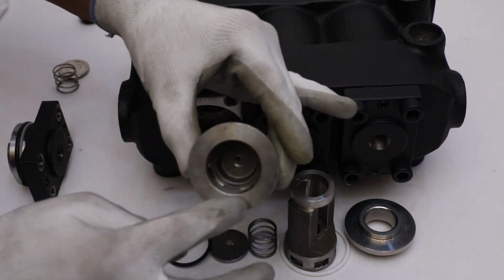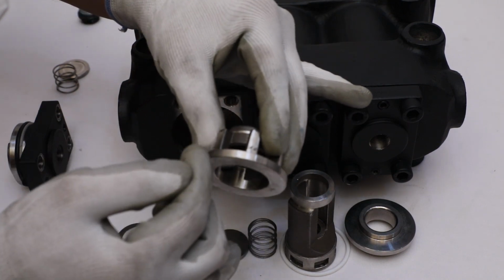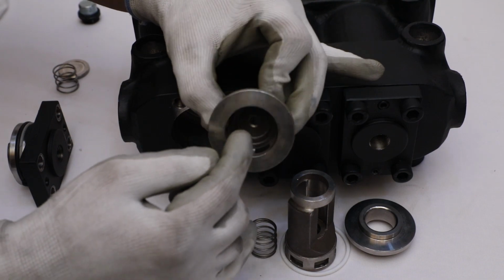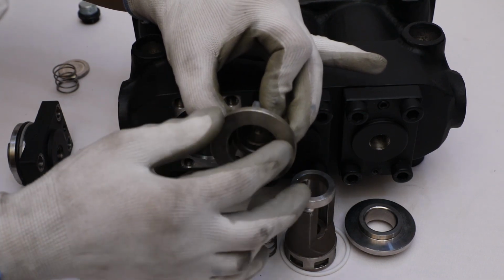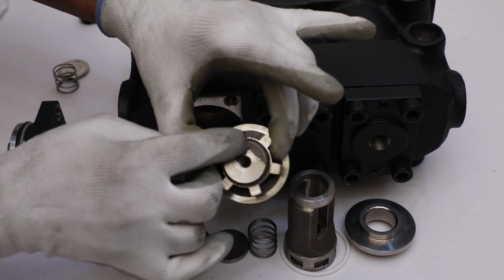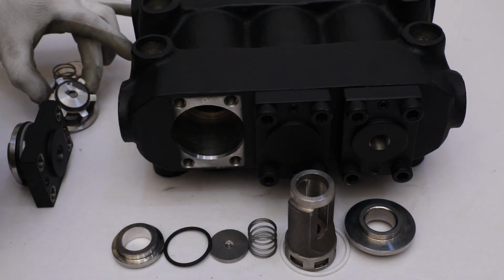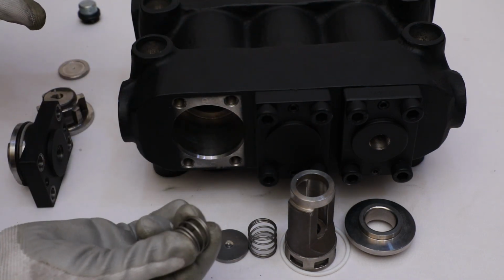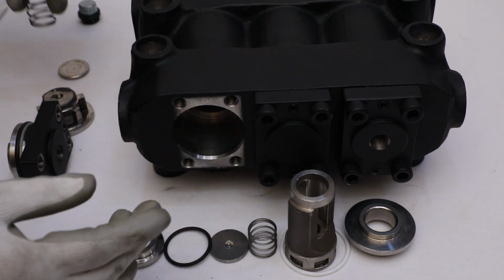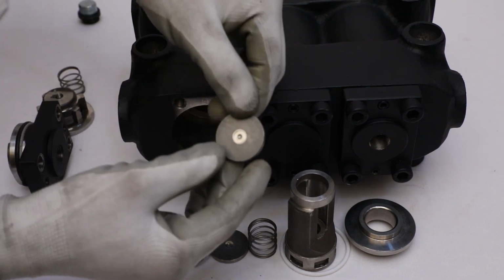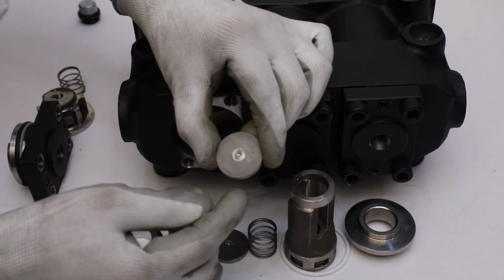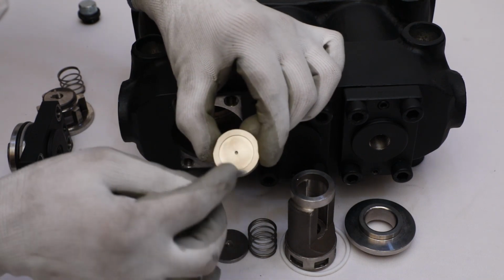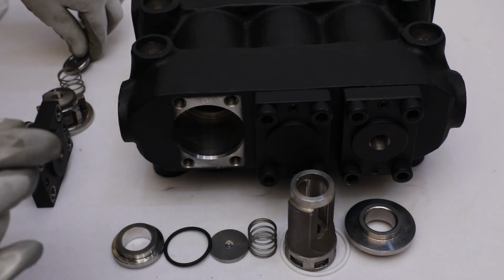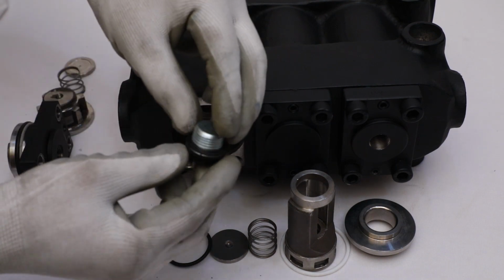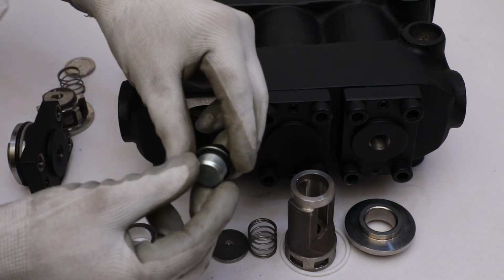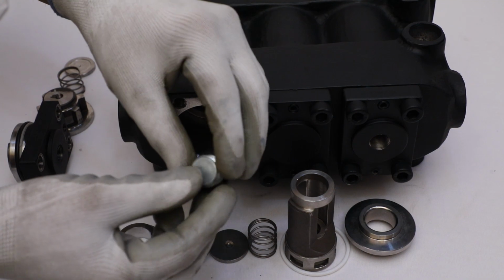Check flat surface, periphery and inner surface of discharge valve guide. Check stiffness of helical spring. Inspect both sides of the surface of suction and discharge valve plate for any wear and dent marks. Check thread of solid plug for damage.